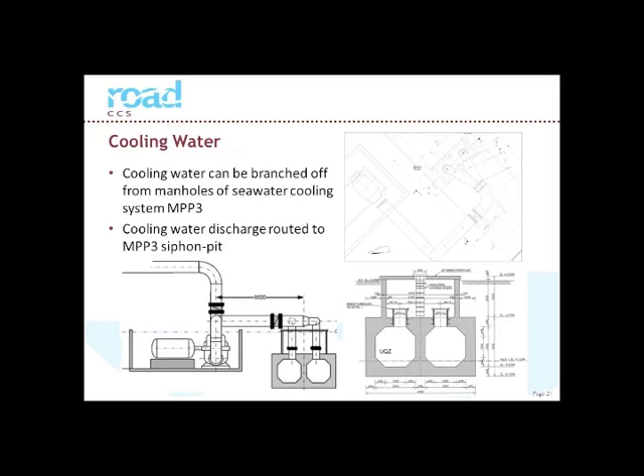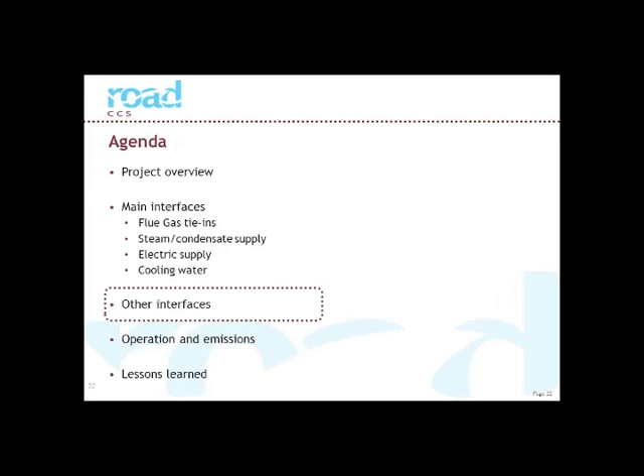The MPP3 cooling water ducts run under the plot of the capture plant, so the connection points are close by. The suction pipe of a booster pump that pumps the seawater through the cooling water system of the capture plant is connected to 2 manholes. There are no changes to the seawater cooling of the power plant, and that is the main advantage of this solution. Now I will shortly mention some other interfaces between the capture plant and the power plant.